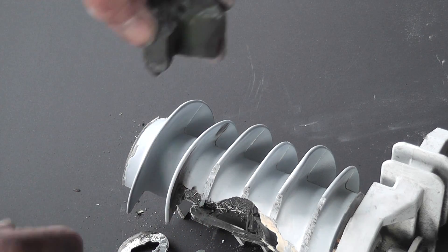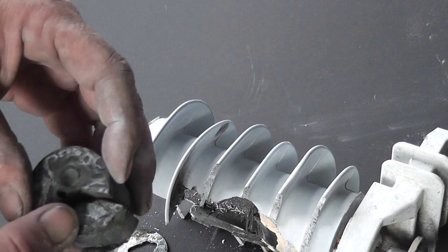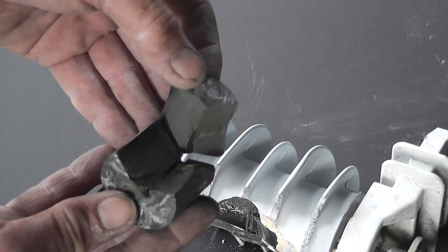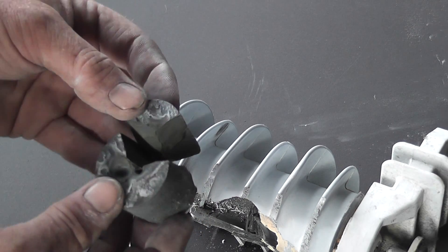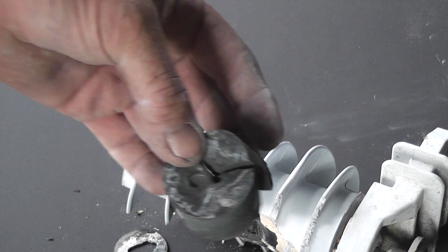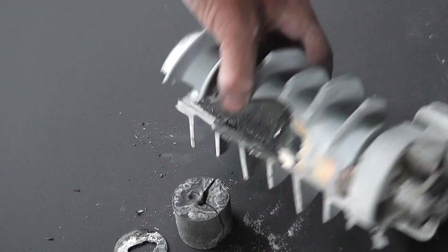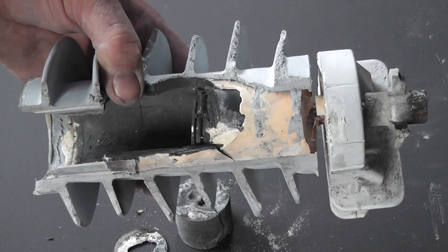This one has failed - well, obviously it did what it's supposed to do: take the feeder out. There's been a bit of heat in there. It smells like a bit of carbon - carbon with iron type material. Not sure what it exactly is. But yeah, that's the autopsy on this device.